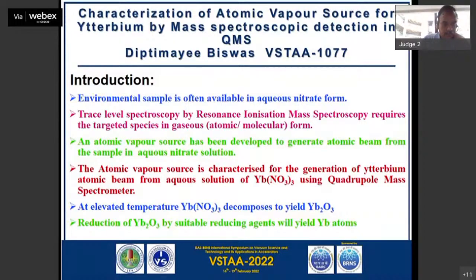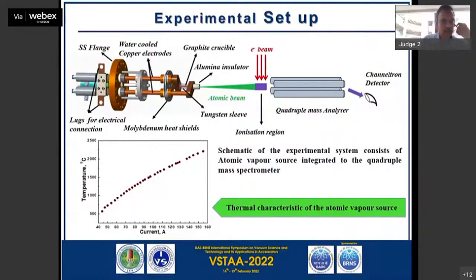The concept is that at higher temperature, Yb nitrate decomposes to yield ytterbium oxide, Yb2O3, and using a suitable reducing agent, that Yb2O3 reduces to Yb atoms. The experimental setup consists of an atomic vapor source and one quadrupole mass analyzer system. The atomic vapor source consists of a graphite crucible, which is held by two water-cooled copper electrodes, and it is resistively heated. So the sample present in the graphite crucible gets heated and volatilizes the atoms.